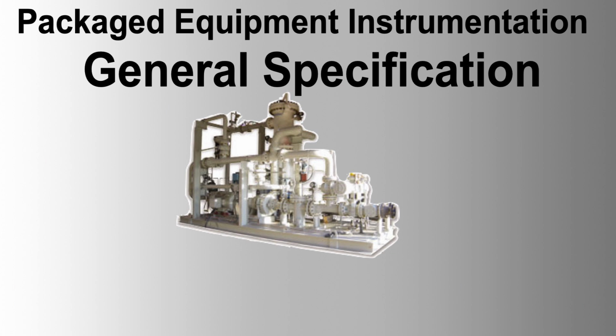Local control panel: PLC-based control system for monitoring and control, Ex type for specified hazardous area classification, with front door access and integral sunshade. Wiring should be low smoke emission, halogen-free, and flame retardant, with provisions for online testing without affecting operation. Tubing and fittings: all instrument tubing and fittings shall be SS316, with process fittings rated at a minimum of 3,000 PSI.